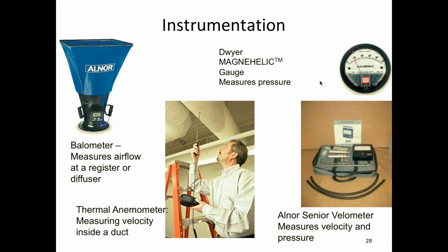So in this case, here's some more instrumentation that you might see. This device up here, the blue thing, is called a balometer. It's not an anemometer. It doesn't measure air velocity. It measures air flow, the quantity of air that's flowing in cubic feet per minute. This one is designed this way with those two handles so you could hold it up over diffusers in the ceiling and actually measure how much is coming out of each diffuser when you're testing air.